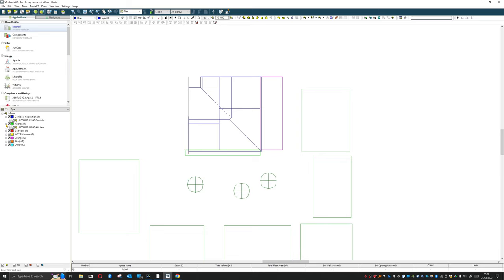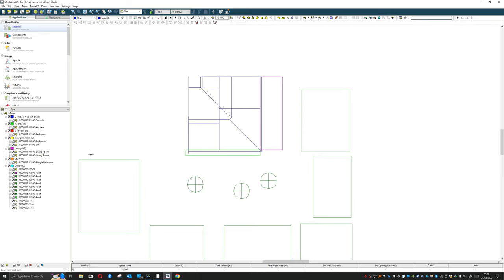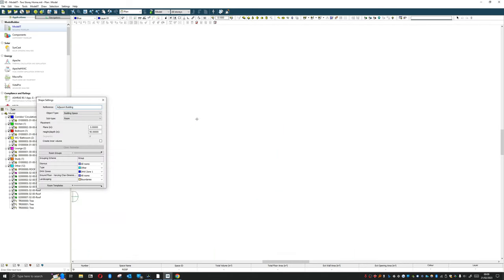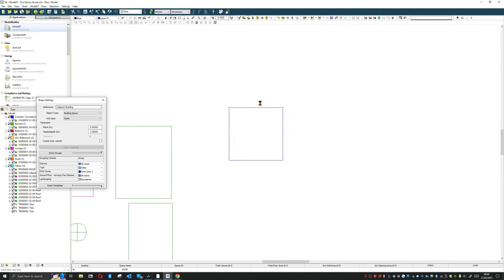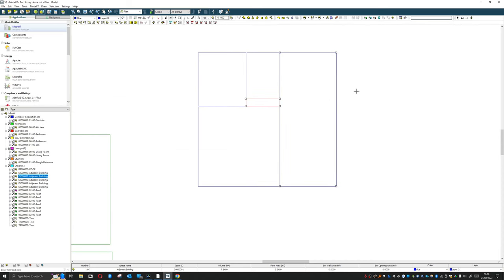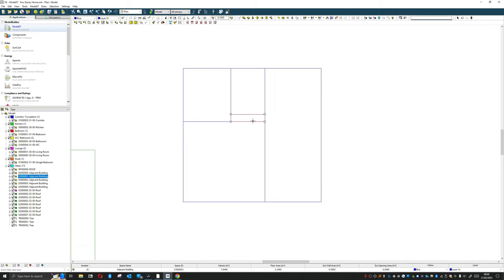A void within a building is a space that is internal - it takes up some of the internal volume of a building but doesn't have any heat gains associated with it, so the room is left to be free running. We can assign this in IES. As an example, let's say we have a 3.5 metre floor-to-floor plan with a simple building, and inside there's a riser of some description with rooms around it. That riser doesn't have any heat gain in it - we don't really want it in our energy balance. Things like voids can be risers or lift shafts.